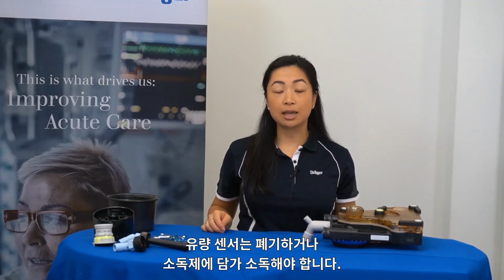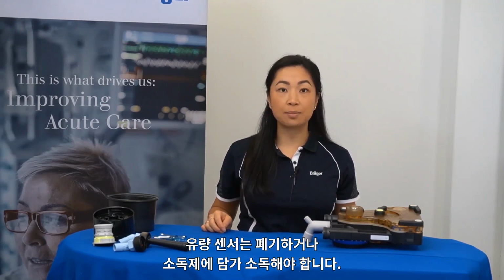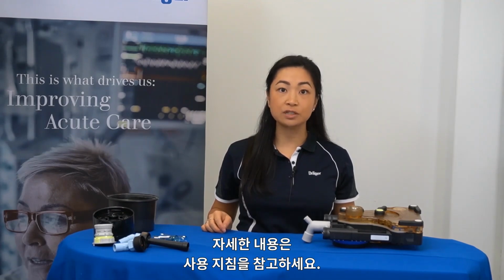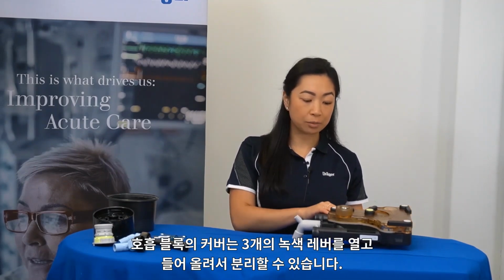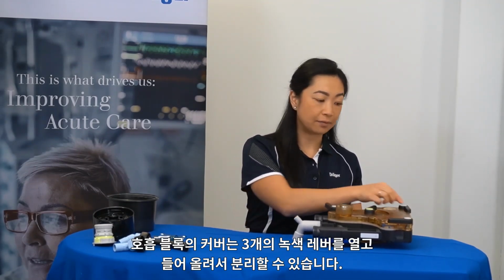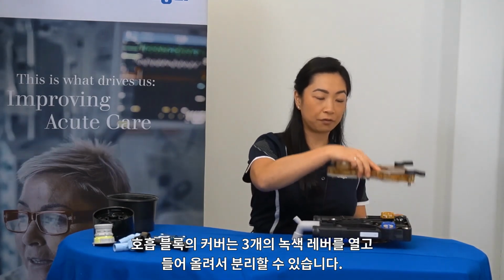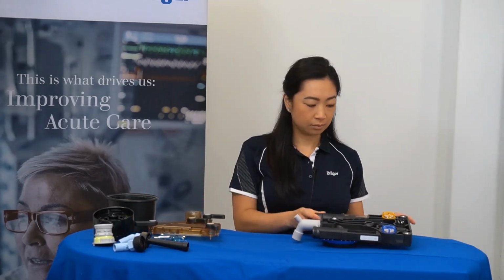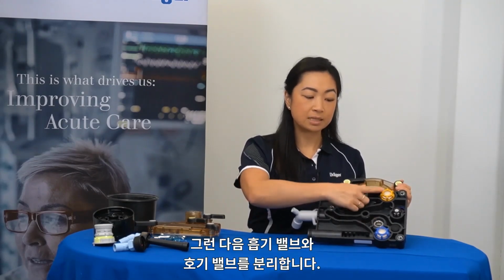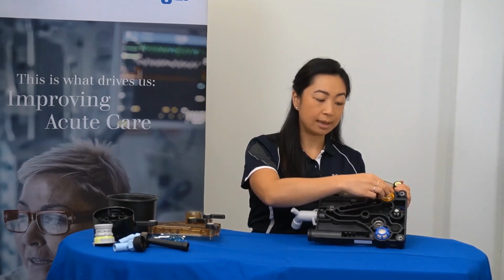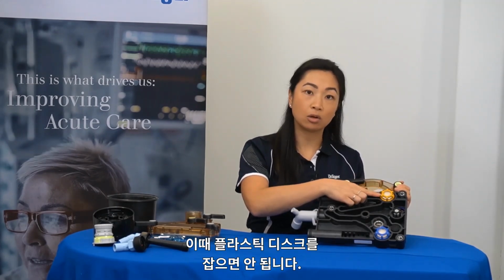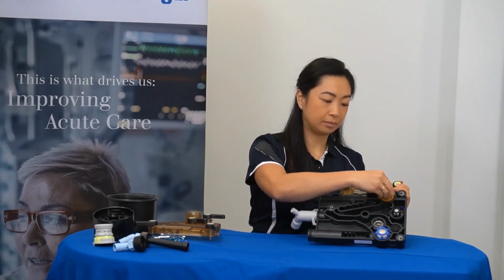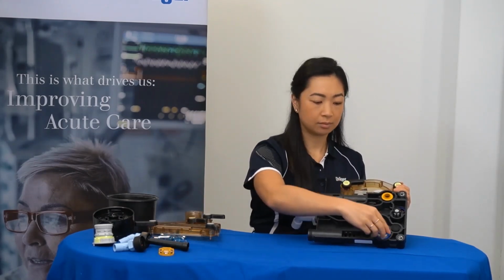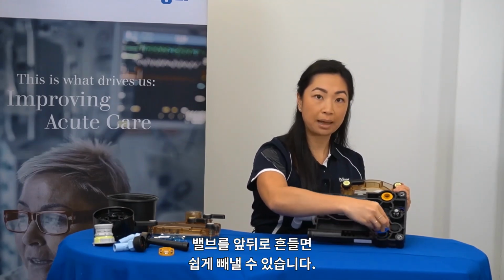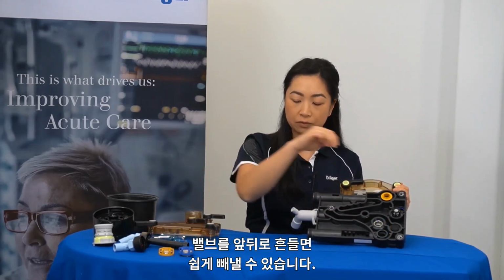Your flow sensors should either be disposed of or disinfected via immersion. Please refer to the instructions for use for further information. The cover of the breathing block can be removed by opening up the 3 green levers and lifting off. Now, the inspiratory and expiratory valves can be removed. Ensure that you avoid holding onto the plastic disc. A forward and backwards rocking motion will help you remove the valves.